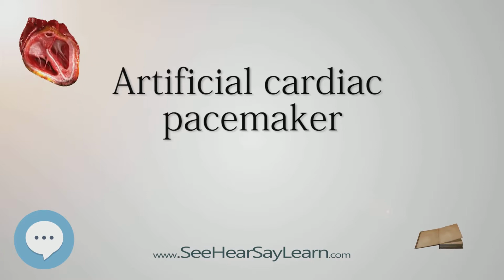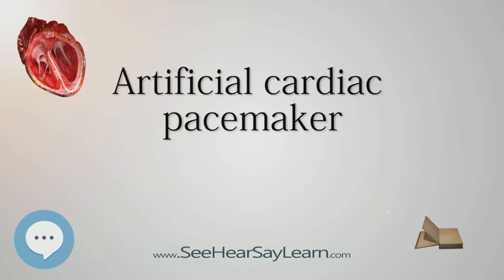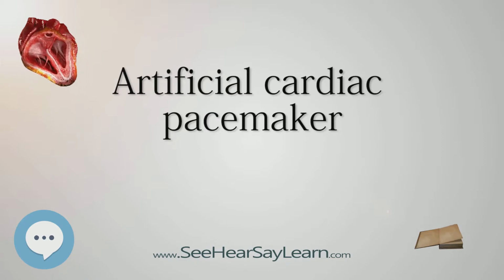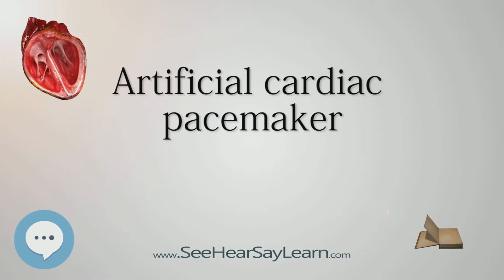Periodic pacemaker checkups. Once the pacemaker is implanted, it is periodically checked to ensure the device is operational and performing appropriately. Depending on the frequency set by the following physician, the device can be checked as often as is necessary. Routine pacemaker checks are typically done in office every 6 months, though will vary depending upon patient/device status and remote monitoring availability. At the time of in-office follow-up, the device will be interrogated to perform diagnostic testing.